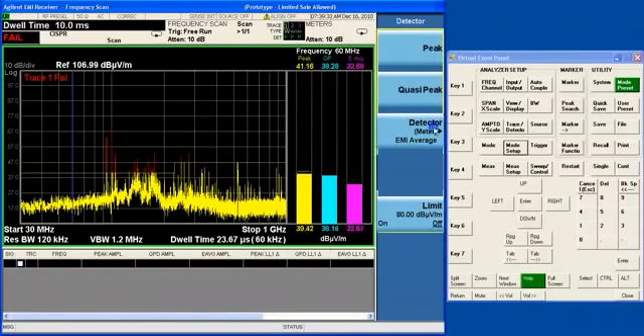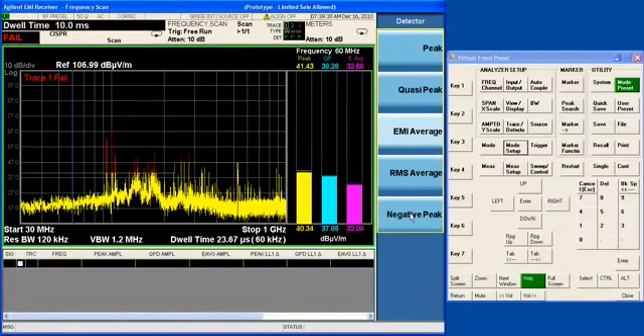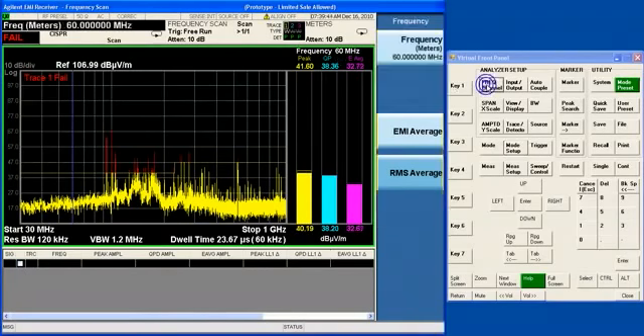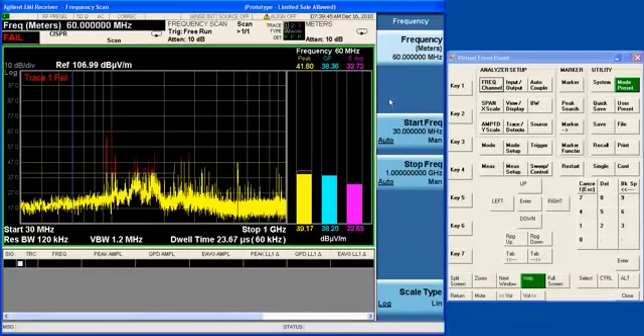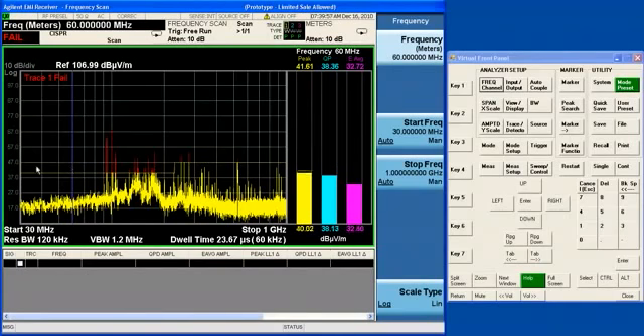We have also the RMS average and negative peak detectors available on the meters. The meters are showing you the instantaneous value, in this case at 60 MHz. You can set the frequency of the meters to any value you want. The meters are only visible when you're not scanning, because when you're scanning, you're moving through a range of frequencies, and the meters are available only at a spot frequency.